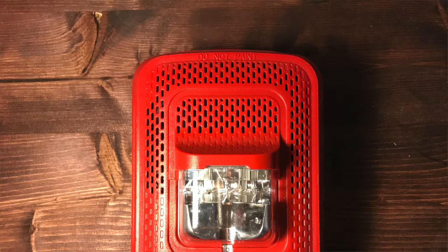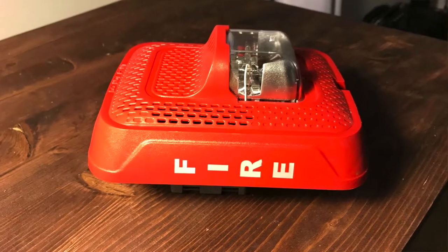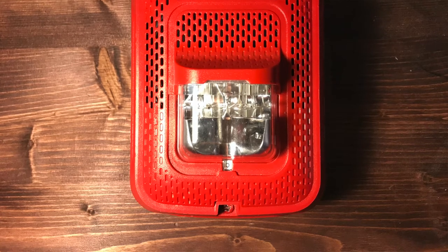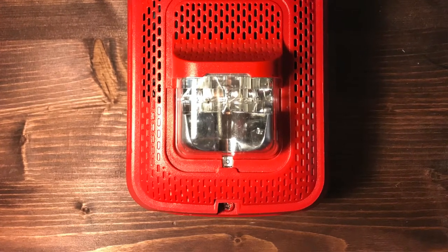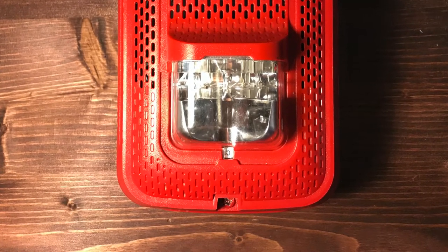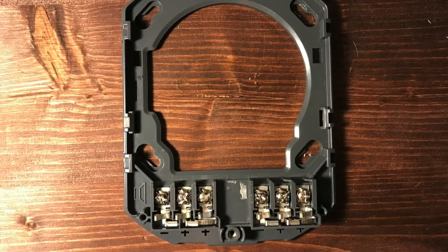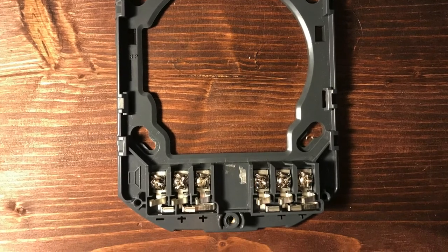Up at the top we have 'Do Not Paint.' On the sides we have these little bezels which say 'Fire' on them, and I'm pretty sure you can buy attachments that say different things depending on your situation. Going down we still have the grill design, but the grill is closed instead of open, and we have the Candela indicator window right under the strobe, which looks similar to other L-Series products. Coming down we have that same grill design at the bottom — again it is closed because the speaker is up top. Then we have the mounting screw. Taking off the mounting bracket, we can see it has six wire terminals: three for the speaker — one negative and two positives — and three for the strobe, one negative and two positives as well.